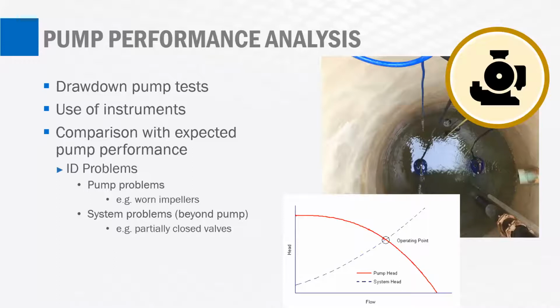Once we get that O&M staff interview done, then it's important to go out to the site and start with the pump performance analysis. This starts with the drawdown test. With the drawdown test, we have to measure the inflow and the pumped flow. There are various ways this can be done. You can have an expensive audit performed, where lots of instruments are used, or you can simply measure the flow coming in. You could use things such as a tape measure or a level instrument, but it's important to get the inflow in addition to the pumped flow. Use the geometry of the wet well to determine the flow coming in and going out of the pump station wet well.